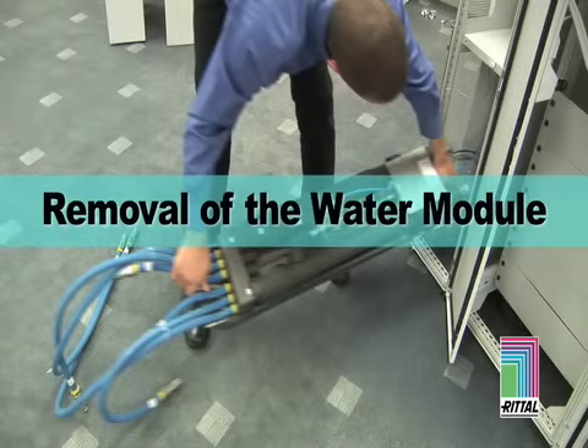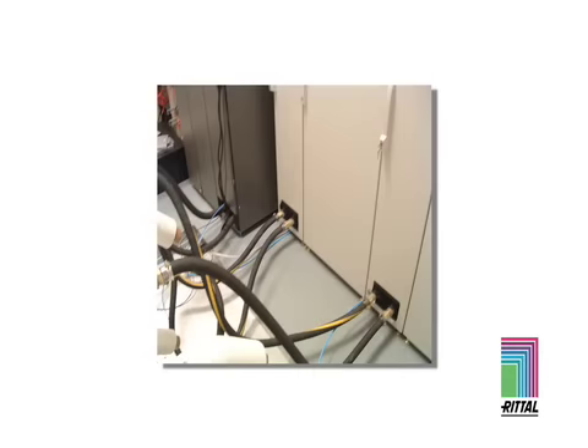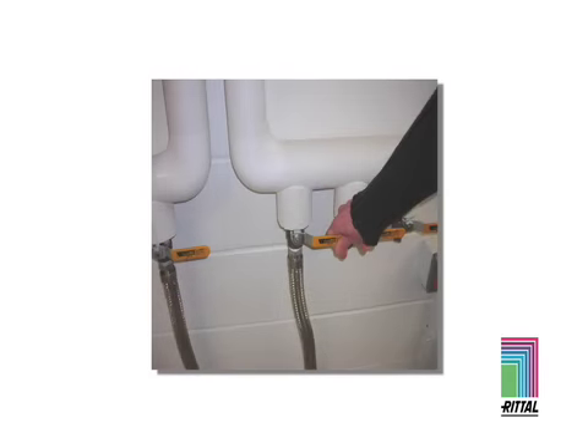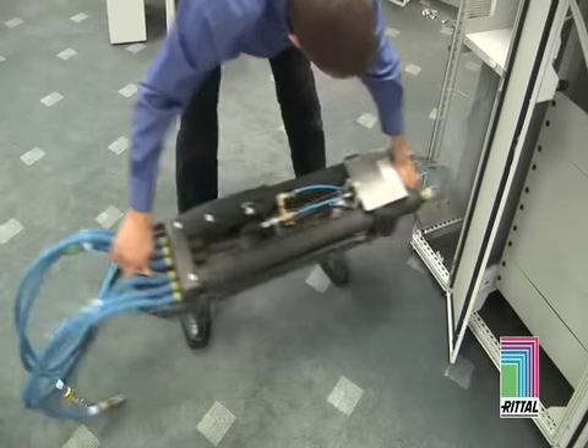Removal of water module. First, disconnect the chilled water lines from the LCP tray. Make sure to shut off any supply and return lines. Now remove the 2 retaining screws and remove the tray from the unit. Installation is simply the reverse of these procedures.